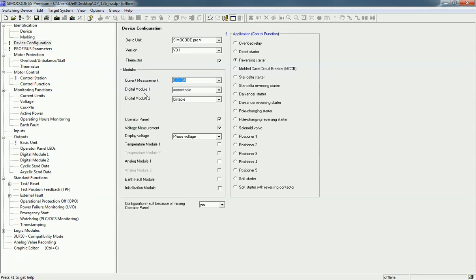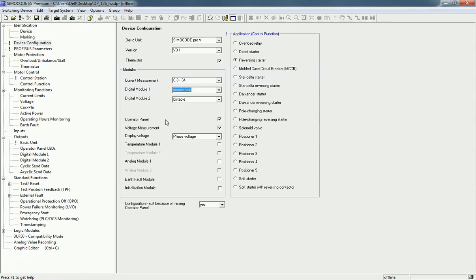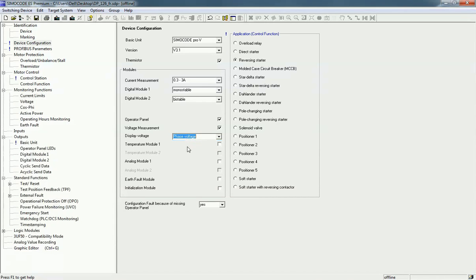If you have added an extra digital module, you can select it as per your hardware. Right now we have a monostable digital module. For the operating panel, we have one connected with the SIMOCODE kit, so I will enable this option. We also have a voltage measurement unit integrated with the current and power measuring unit. You can display line-to-line voltage or phase voltage — I will select phase voltage, so the operating panel will continuously show the phase voltage.